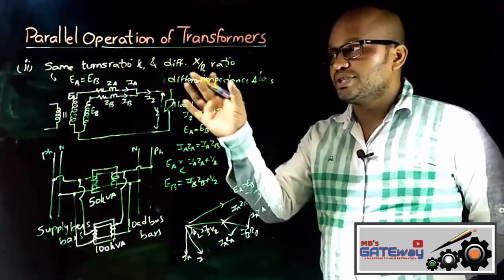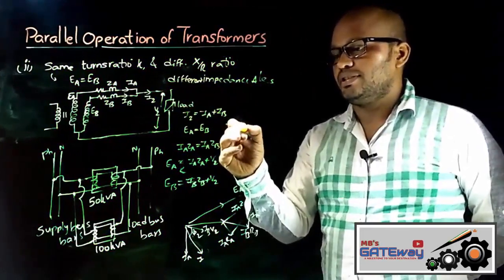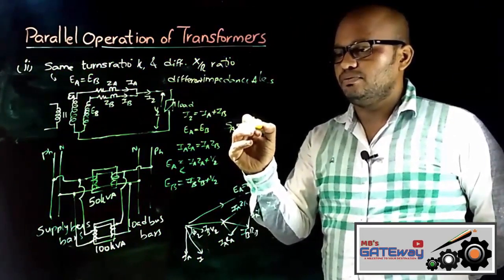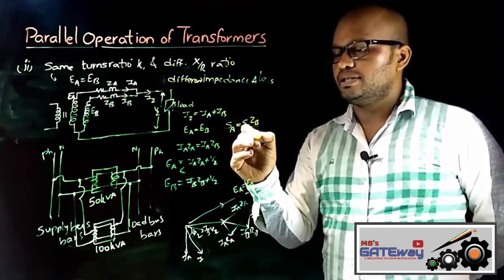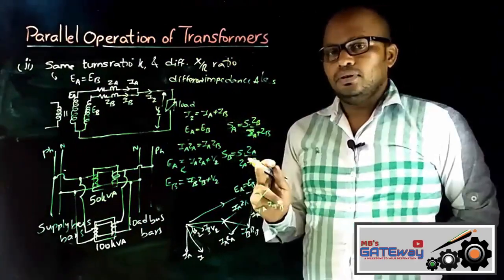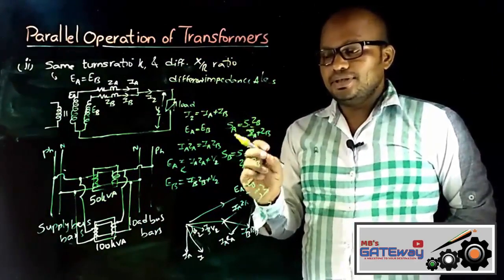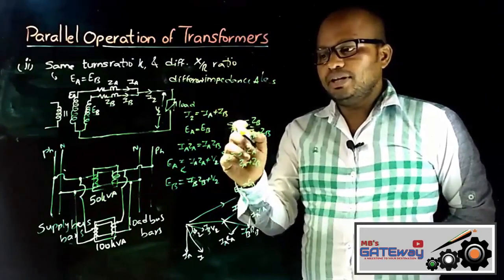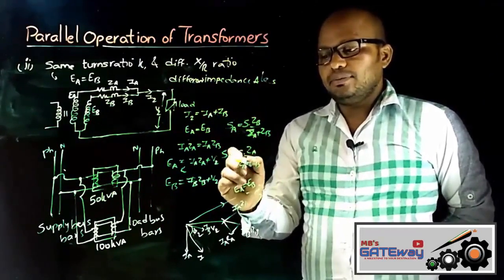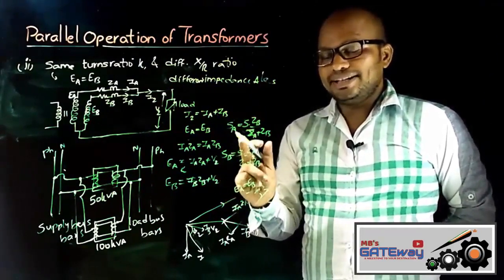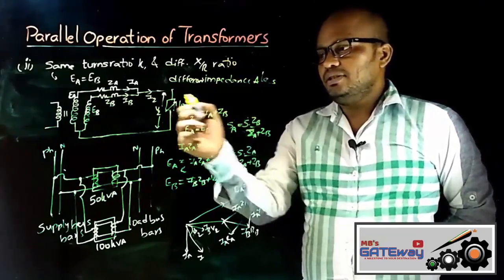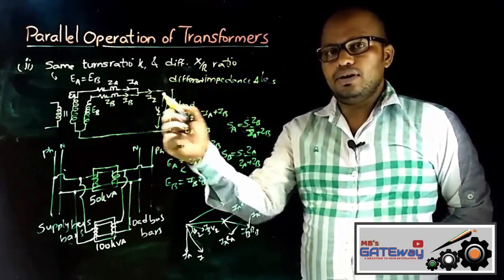The important equations corresponding to this case are SA is equal to S into ZB by ZA plus ZB. Here SA and SB represent the part of the load shared by transformer A and the part of the load shared by transformer B. S is the load rating, that is, V2 into I2.